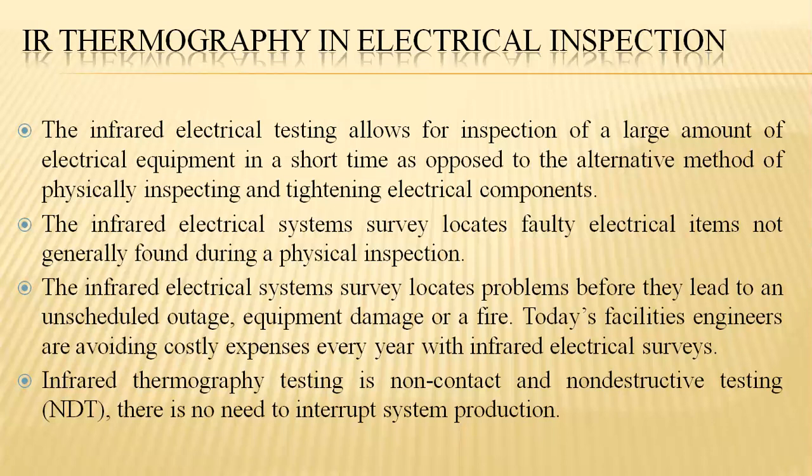Even in physical inspection, devices such as voltmeters could play a major role in identifying faults. But going from one material to another is a very big and time consuming task. With IR thermography, it clearly identifies which part has the deviation, without contact. Manual inspection needs direct contact. From our subject's point of view, this technology can be utilized for a non-contact mode of inspection strategies.